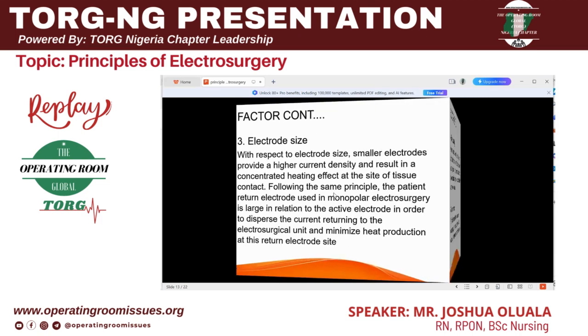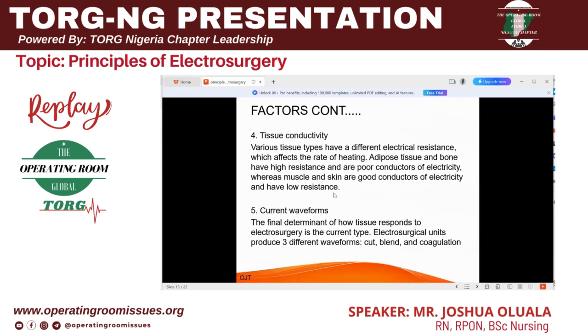So the electrode size also determines the density of the current that is passed across, and also the tissue effect. Then number 4 is the tissue conductivity. Like I said earlier, different tissues have different levels of resistance, and in this case we can see that adipose and bone have high resistance, and that is why many times when we get to the adipose tissue, you have to increase the current in order to have a desired effect, because they are poor conductors. They just begin to absorb the electricity. So it will take more time to achieve the desired effect, unlike in muscle, where once you put it, you get your desired effect.